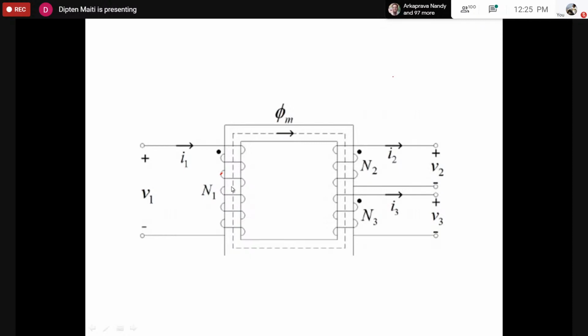One information is missing from the outside, which is not possible to know if you don't open the transformer: whether the coils are wound over the core in the same fashion. Looking from the top, if we consider all the coils to be put over the same core or same limb, whether all the coils are wound in the clockwise direction or in the anti-clockwise direction.